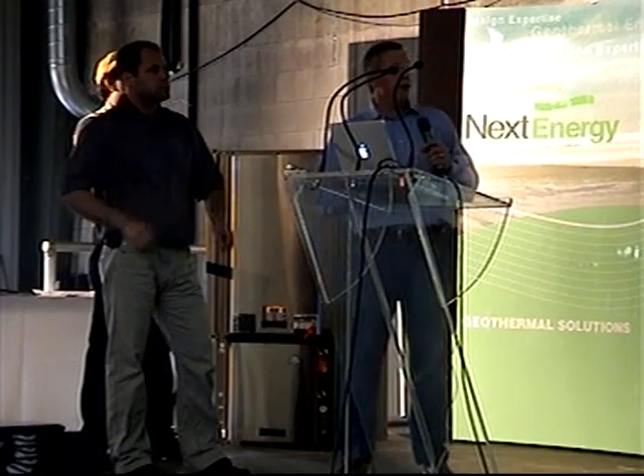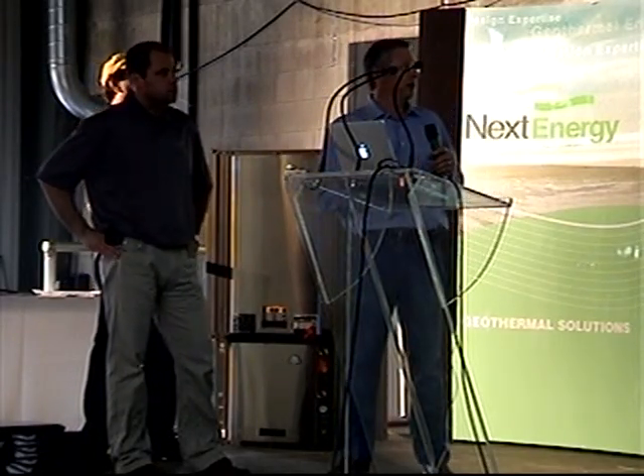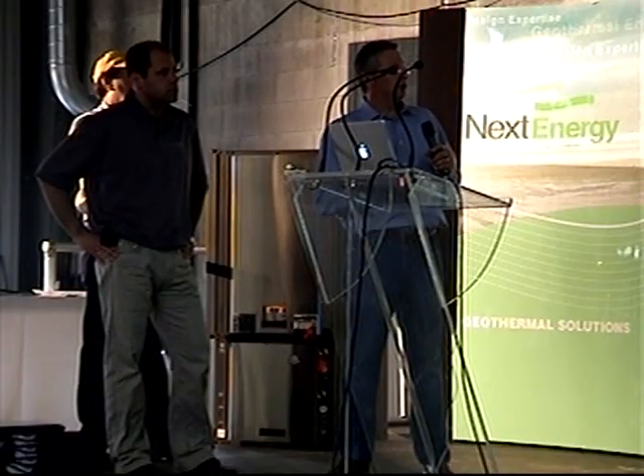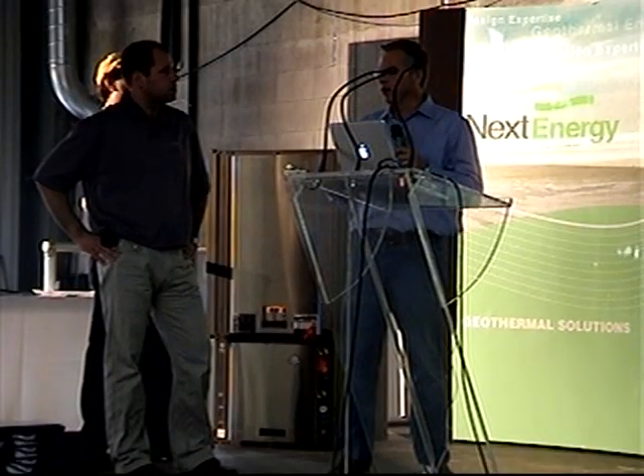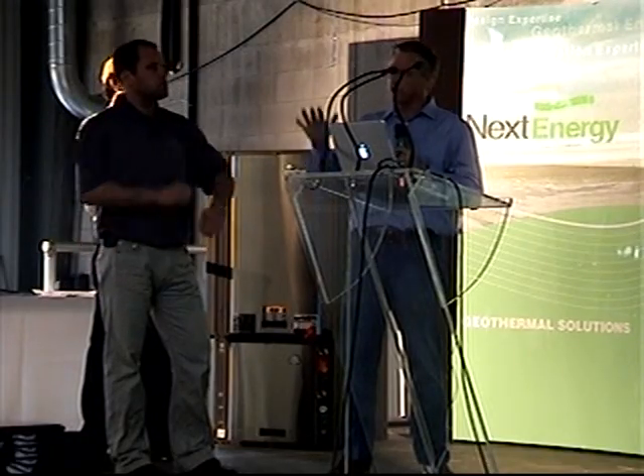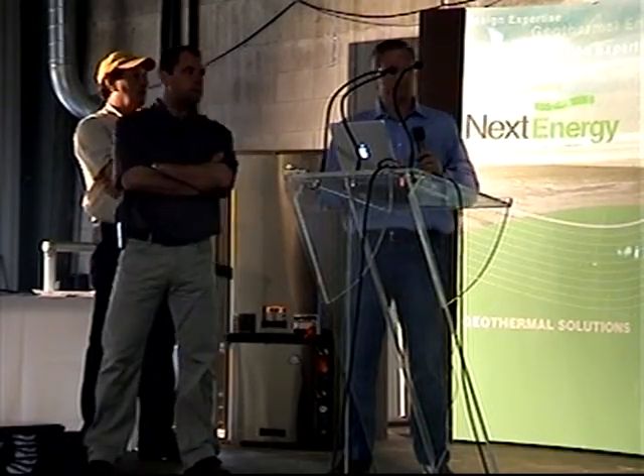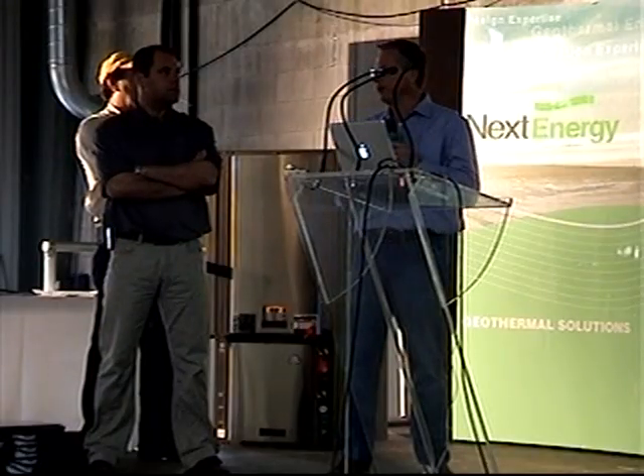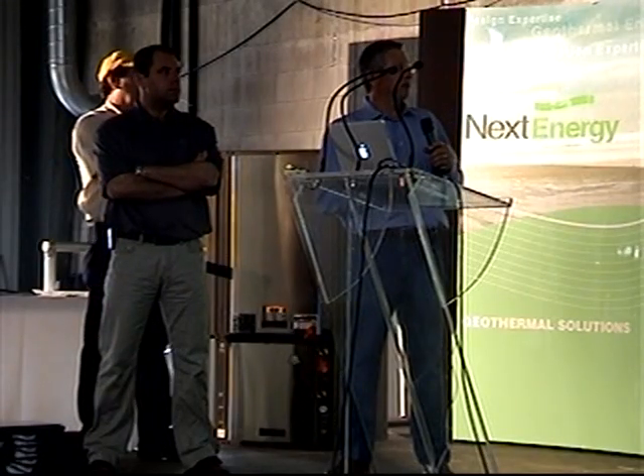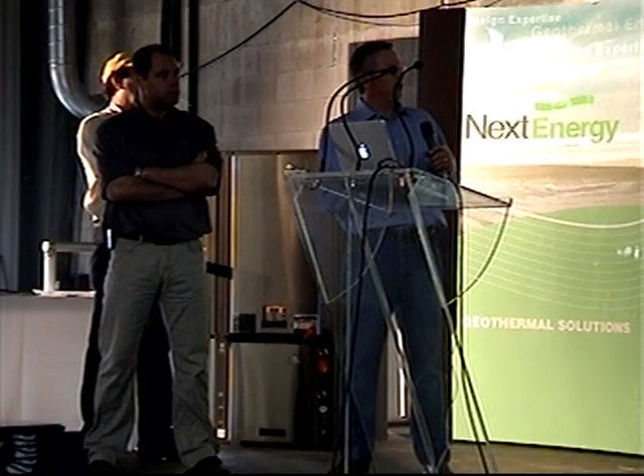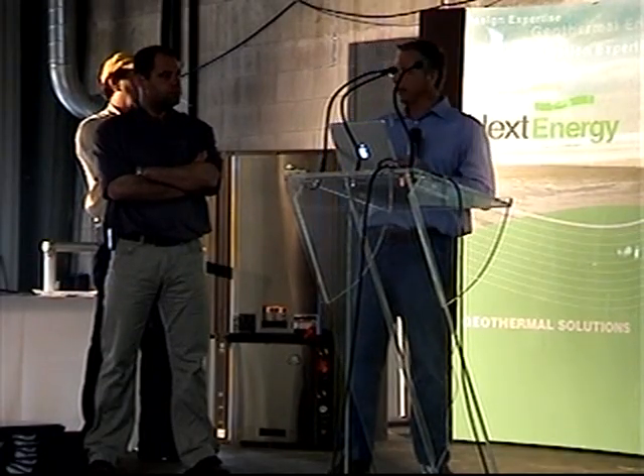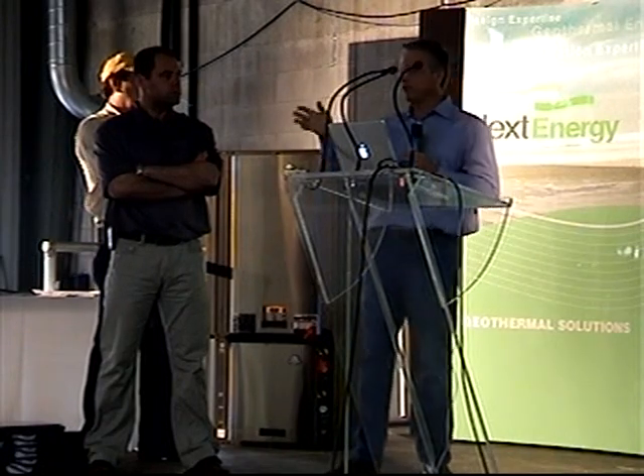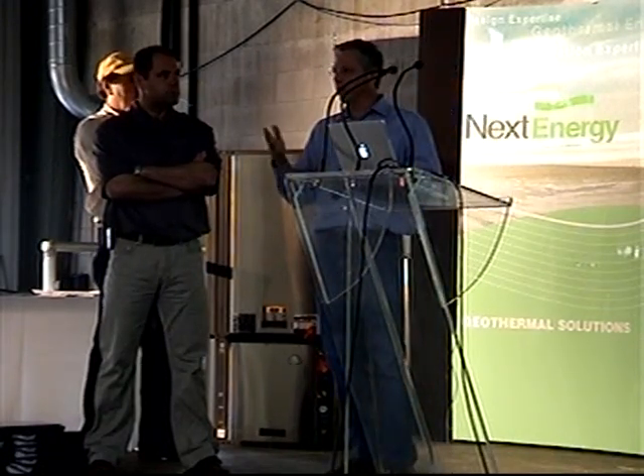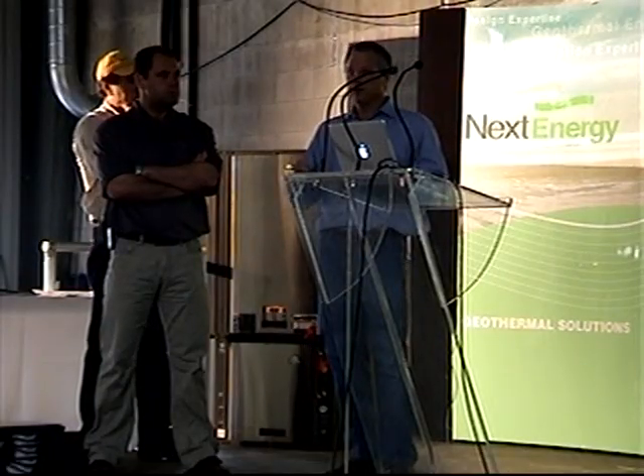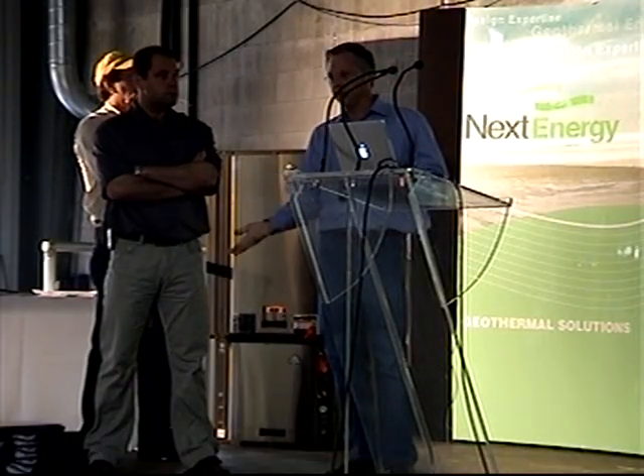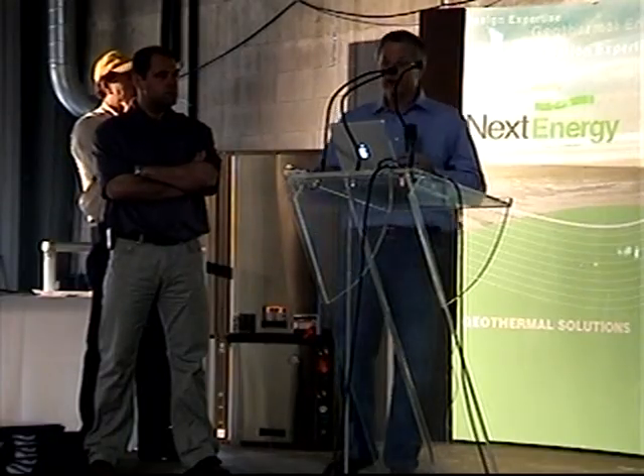You get to pick your CFM, heating, cooling, and auxiliary heat. You get to decide whether you want to run in dehumidification mode or not. If you turn that on, the unit runs on a lower airflow in cooling to dehumidify better, which up here, I think you would use that. I don't know why you wouldn't want it all the time. And it does tell you the airflow you're running at. This little LED will blink 1 flash for every 100 CFM. So if you wonder what airflow it ought to be running at, if it's blinking 12 times and it's off for like 20 seconds and does it again, you've got 1,200 CFM.